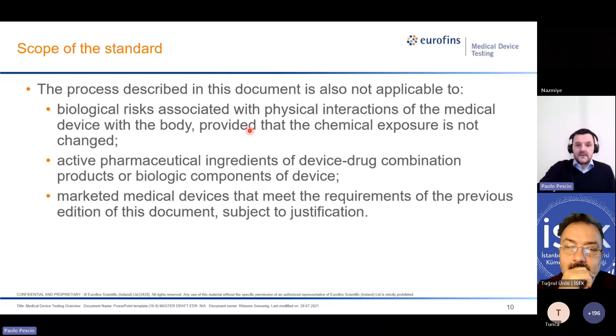the standard? Just to remind you that new clauses were added, and you see here that clause 5, that is probably the most relevant one, toxicological risk assessment within the biological process, was added. This is the main clause describing the entire process. We have a new clause 6, constituent toxicological information, and the way we look for toxicological information. It's not, to be honest, well described how we perform a literature review of the constituent, but at least it states the way we need to look for toxicological information.